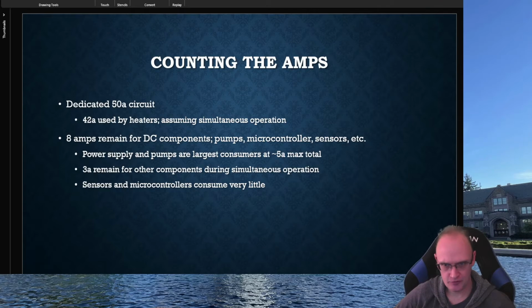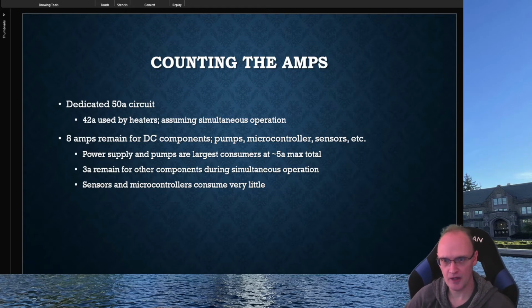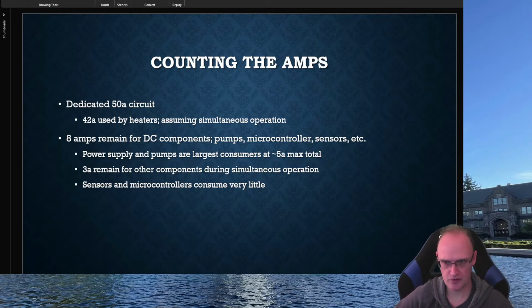So if we have a dedicated 50 amp circuit, that means there's nothing else on it besides our control panel. Then 42 amps, as we just calculated, would be used by these two heating elements in this particular example. And that's assuming, of course, they're both on at the same time. Then we have 8 amps remaining for everything else. Probably the main consideration for most systems like this will be the pumps and the power supply itself. These are going to consume together most of the rest of the amperage that's left over.